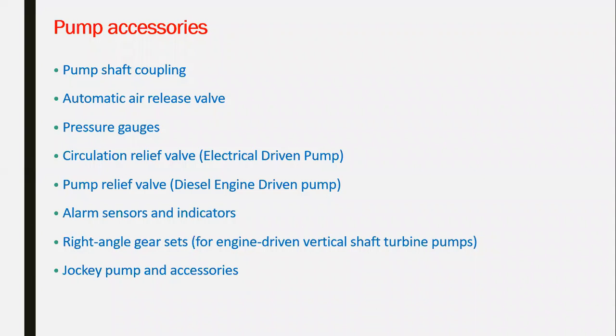Any of the hydraulic systems where you have water, you install automatic release valve, which could be installed on the top body of the pump, or it is installed on the header. It has to be installed to eliminate and take out any air gaps within the water, because the air, if it is in there in the water, it will cause some turbulence and cause hammering within the network. So it has to be eliminated. Why is it happening? Because the compression of the air is not constant. It's like a spring, compressed and depressed, which with the flow of the water is making hammering.